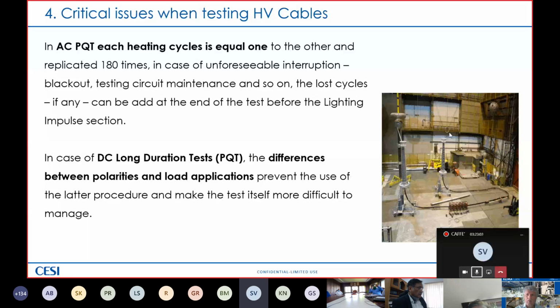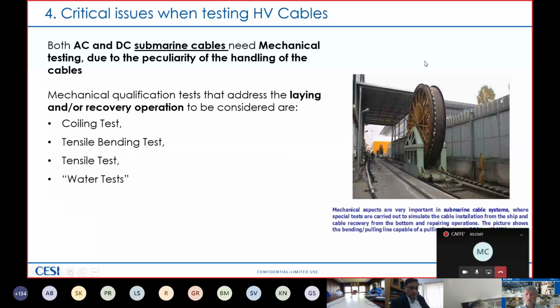Sorry. Yeah, no problem. I was saying that this tensile bending test is performed on the cable system because this submarine cable also includes a factory joint that has to have the same size as the cable. So in principle, the diameter should be the same and has to be tested with this strength in order to be sure that in case of shipping and installation, this will not create a problem. Of course, a repair joint cannot be tested because this has to be prepared on the ship. And again, this can be a weak point of the cable system.